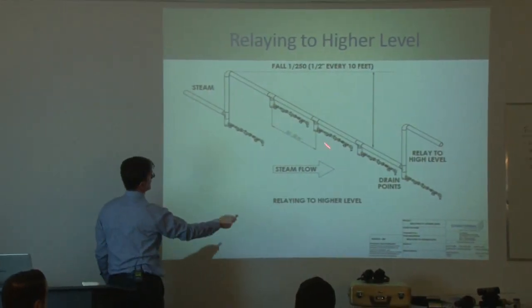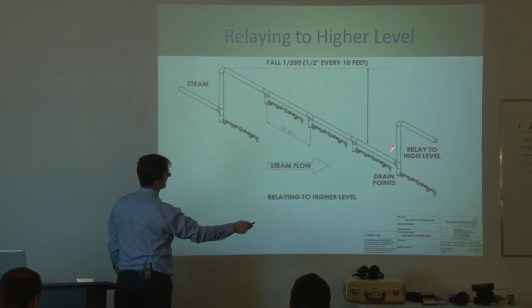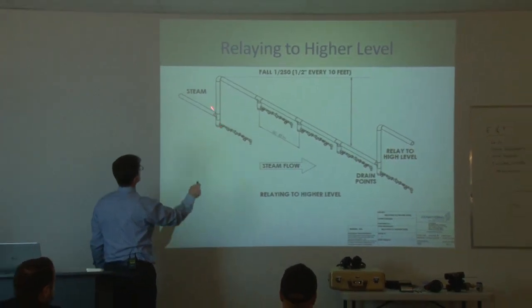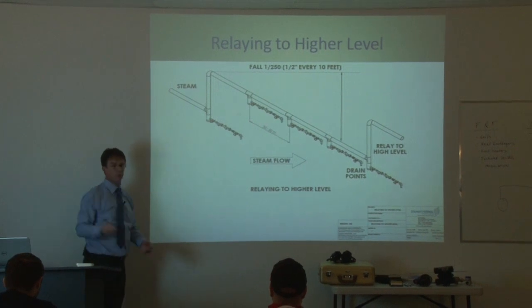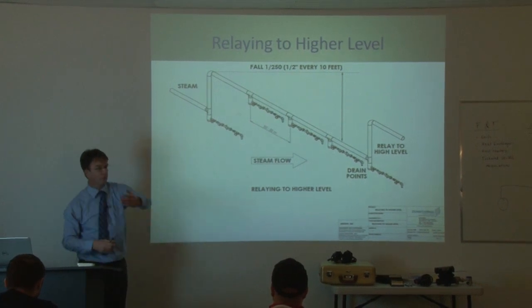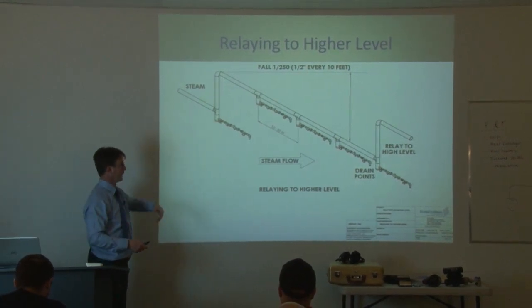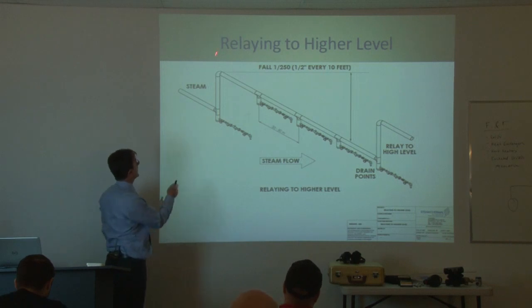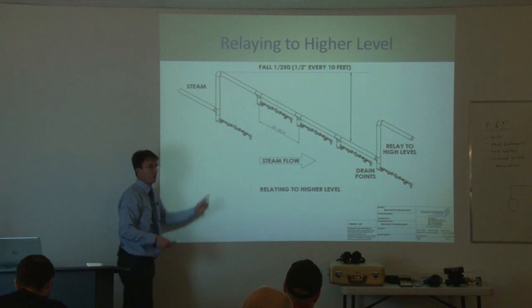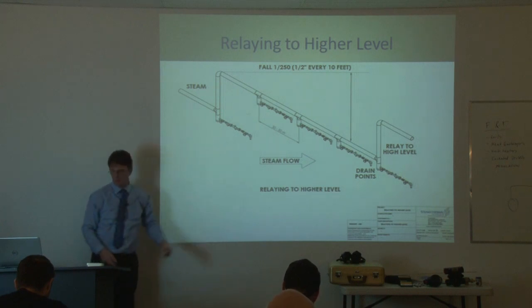It goes down, comes back up, goes down, comes back up. Anytime you have a riser, you need to have a steam trap. So anytime there's a change in direction, whether it's this way, that way, or that way, when it goes down, it's not as important. But when you go up, sideways, sideways, you want to have a trap.